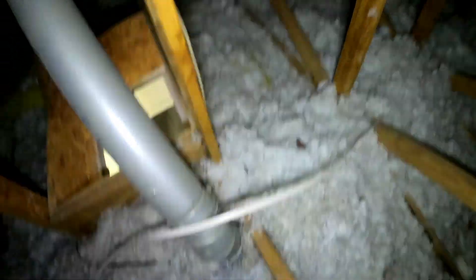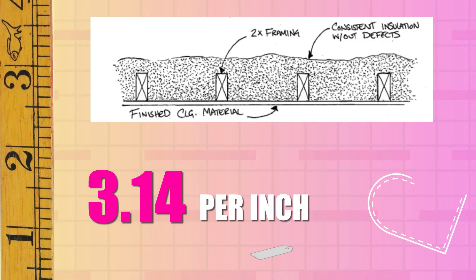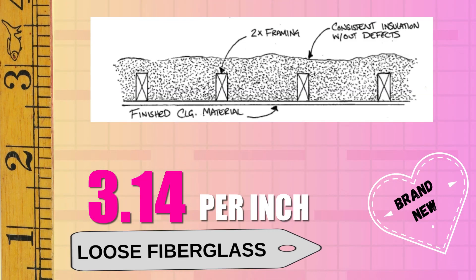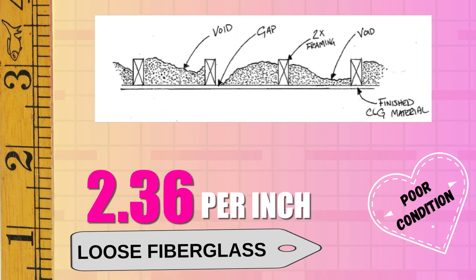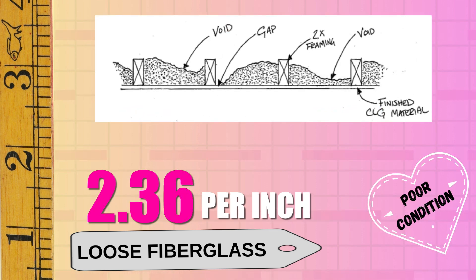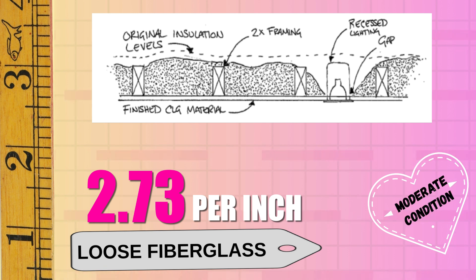Loose fill fiberglass presents as white shreds, pink squares, or yellow shreds. Generally, all three yield the same R-values per inch. New installations provide 3.14 R-value per inch, maintaining this value when well installed, but dropping to 2.36 R-value per inch in poor conditions. Moderately covered attics with loose fill fiberglass should be calculated at 2.73 per inch.